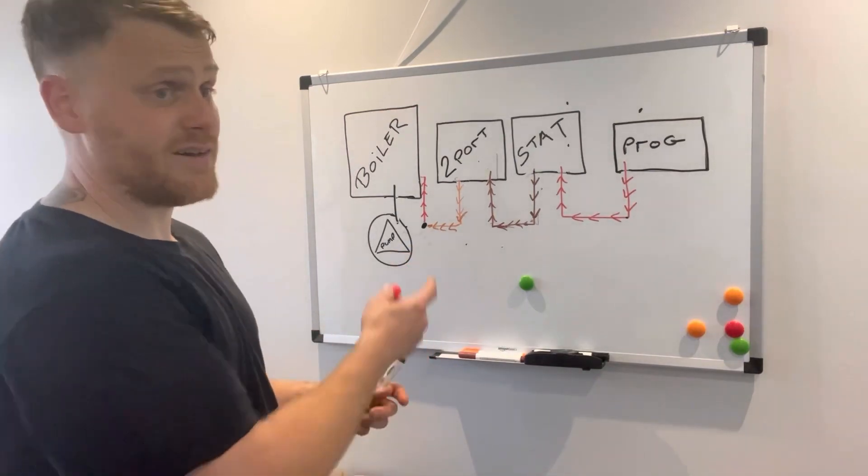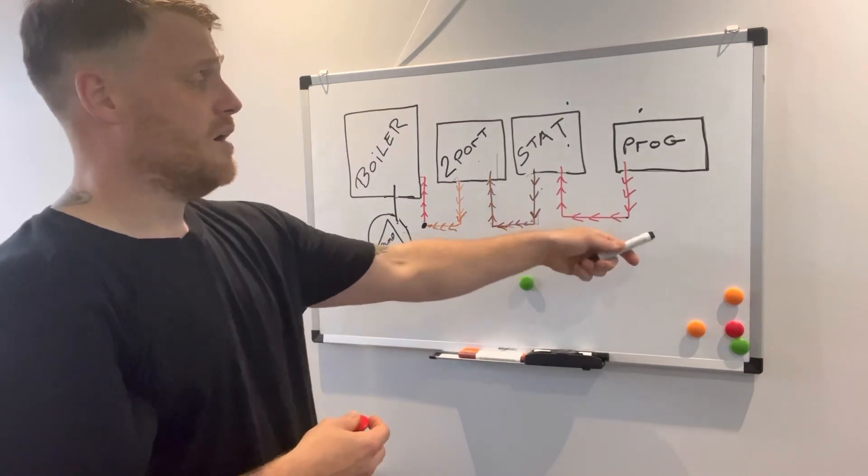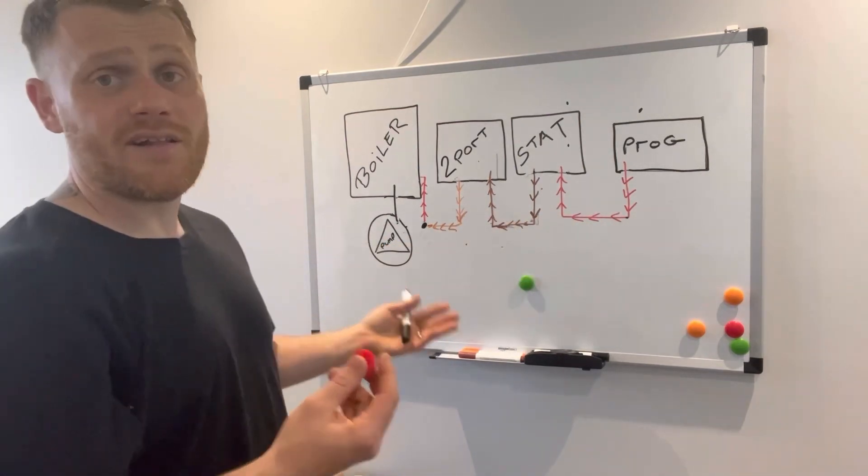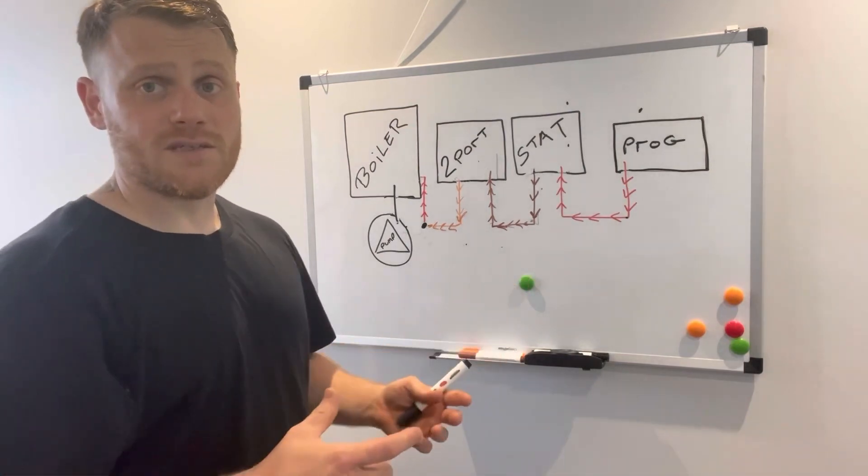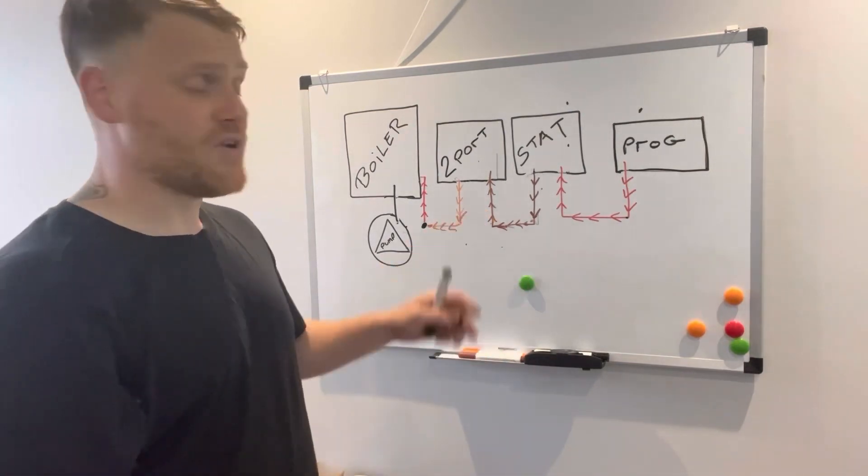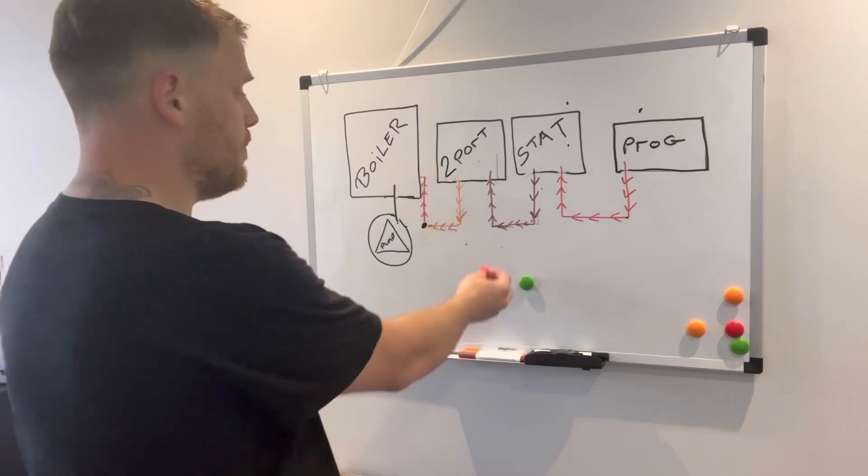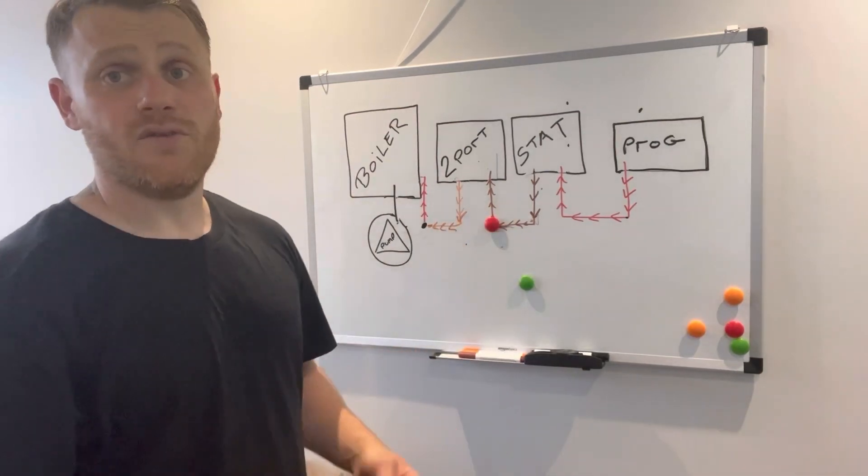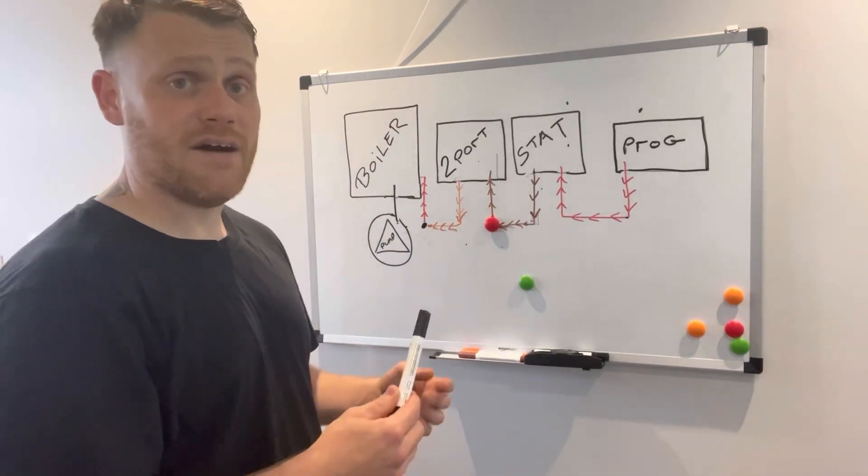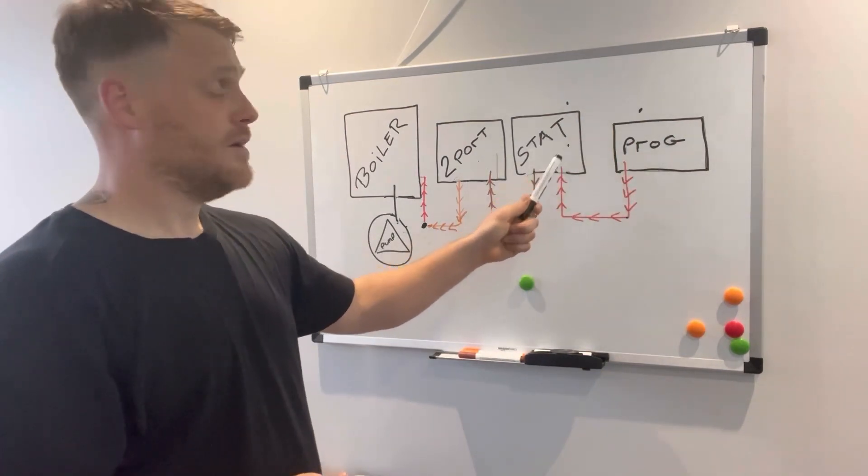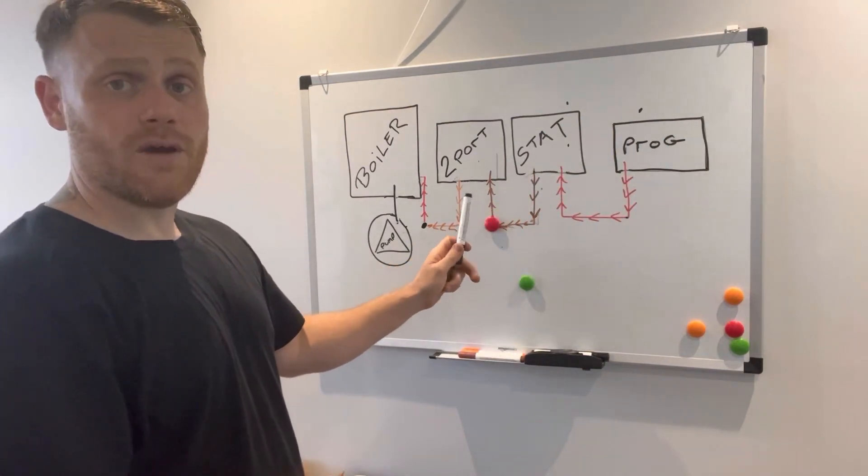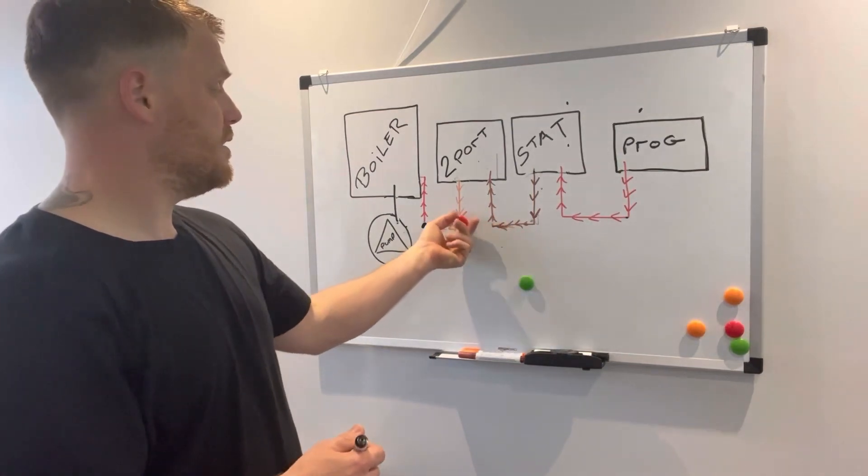That's how I do my fault finding, straight to the brown wire. You can start from the programmer and work your way around, but I just find it easier going to the junction box. Find the brown, put your probe on there. Have you got 240? If you have, we know that the programmer and the stat is fine.